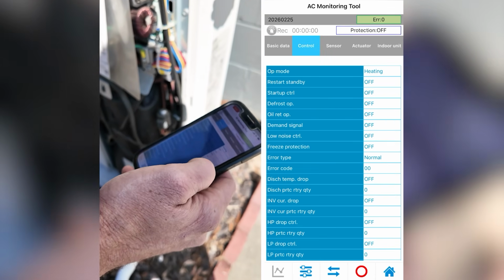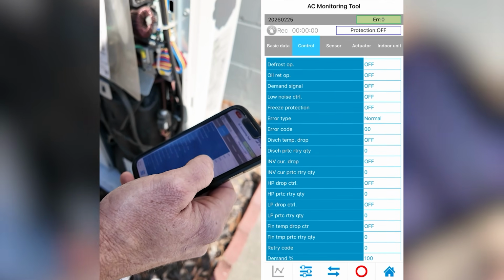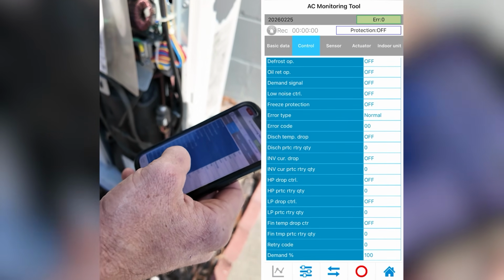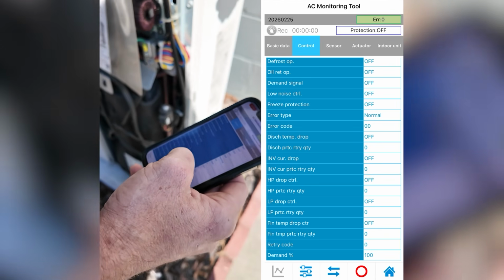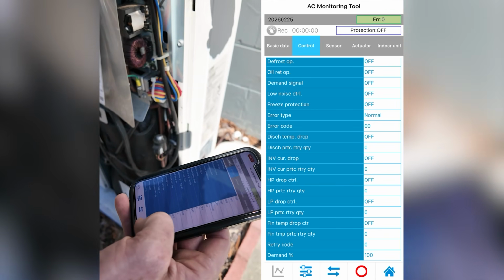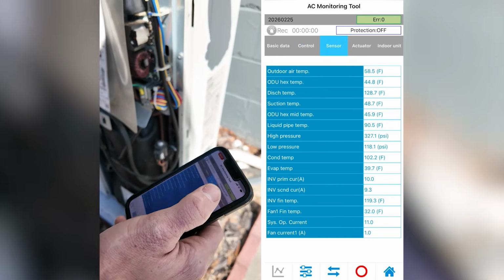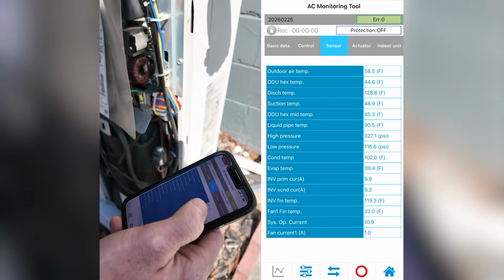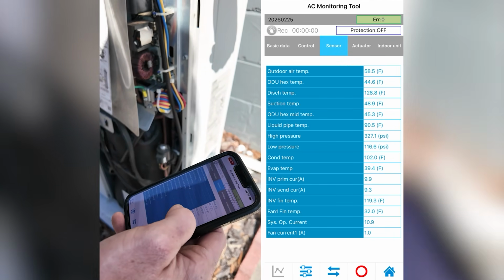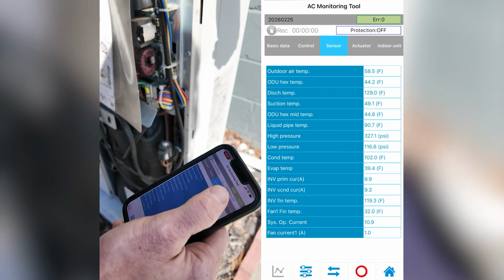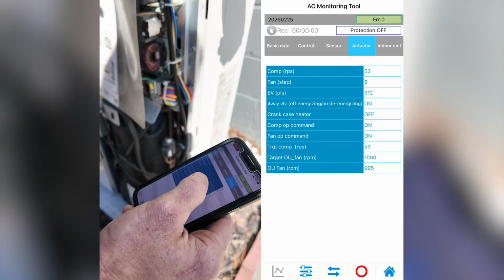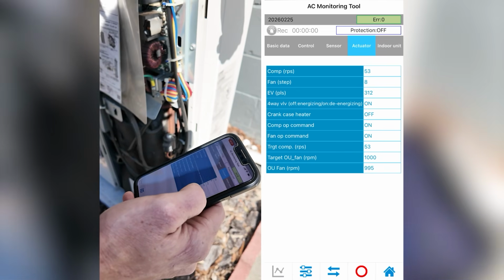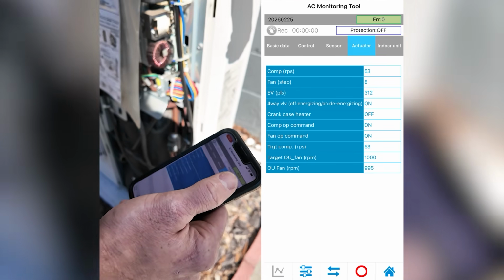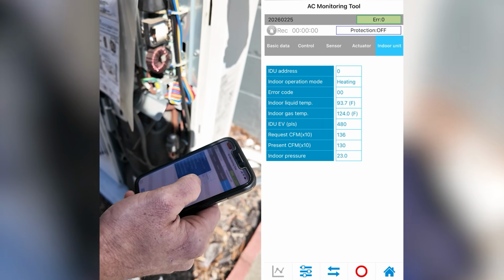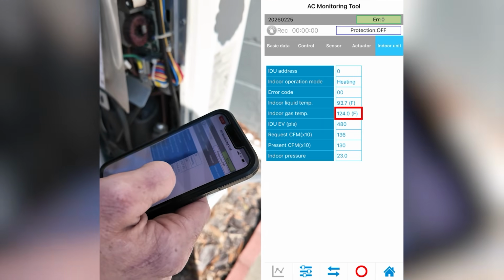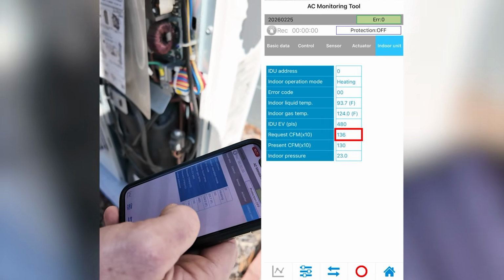And so then from there, I can go through my control and I can see all my control points that I have here. These are all your protection devices, right? High pressure, low pressure, retries, demand percentage. We're demanding 100% capacity on this system right now. I can go to my sensors. These are all the sensors in the system itself, from outdoor air temperature all the way down to liquid temperature. And then actuator, these are your compressor or fan, expansion valve pulses on the outdoor unit, fan RPMs, and then indoor unit. This lets me see everything inside: indoor liquid temp, indoor gas temp, expansion valve pulses, requested CFMs, all the good stuff.